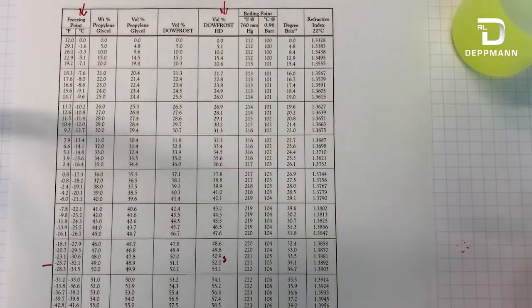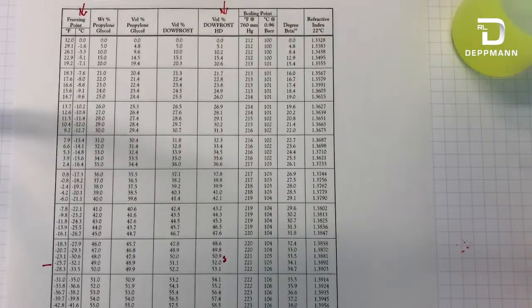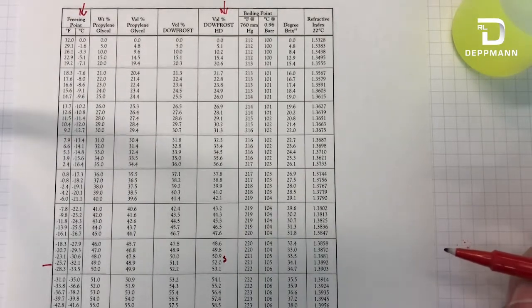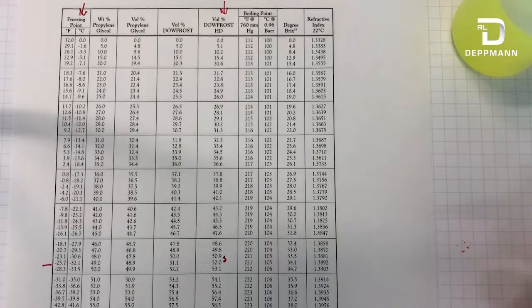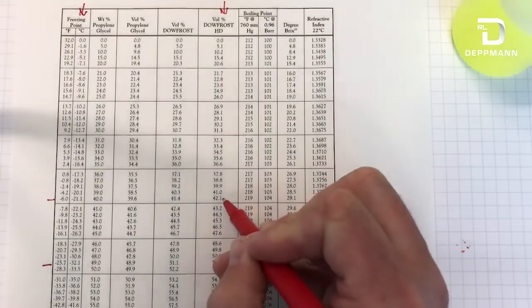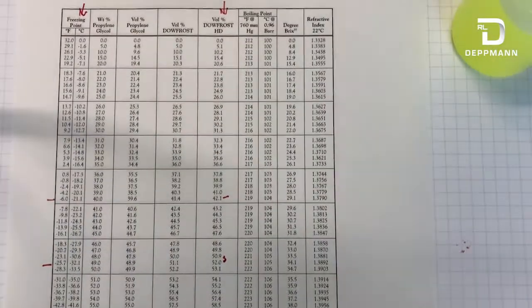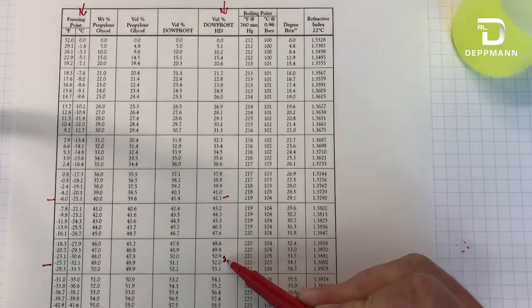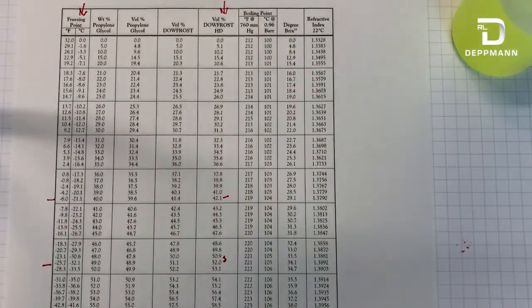But what could happen is over time, a system that's opened and closed, you could start to get your system to become diluted. And for this instance, if we got a reading that was a lower temperature, let's say it was right around negative six degrees, our concentration is then only around 42 percent. We would want to evaluate adding fresh glycol to bring that concentration back up to the 50 percent design.